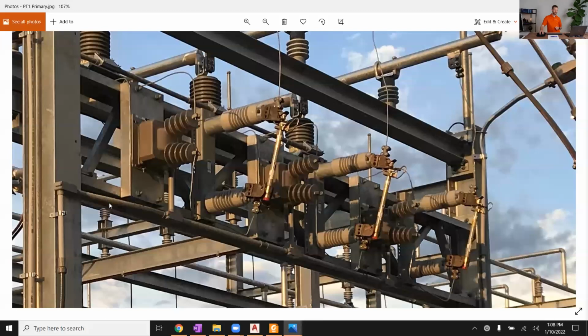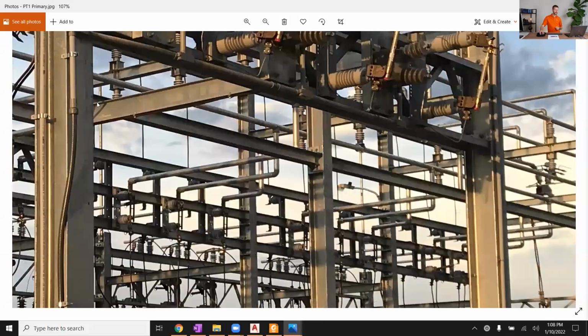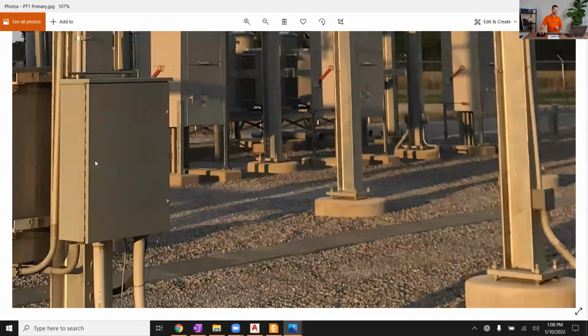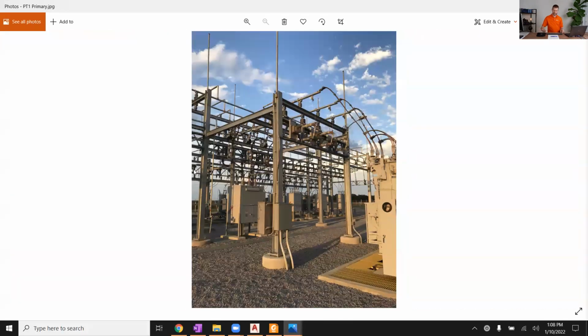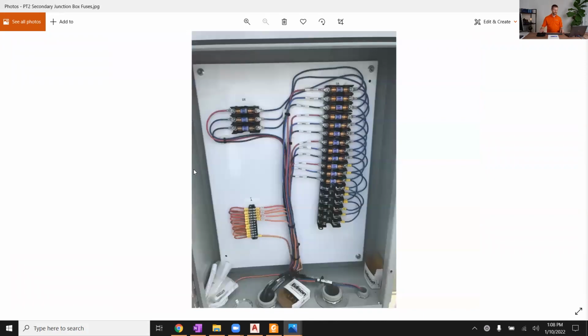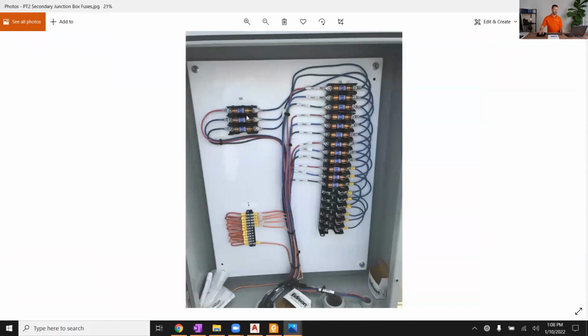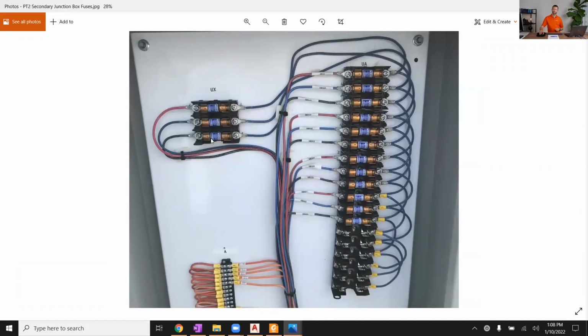And then we bring this down through these conduits, these secondary wires. We bring it into a PT junction box at the base of the pole. I got a picture for you of that as well. This is one example of a PT junction box. You've got coming in phase A, B, C from those three primary PTs up top. And then from there, you can kind of jumper it down. These are fuses that you see here.